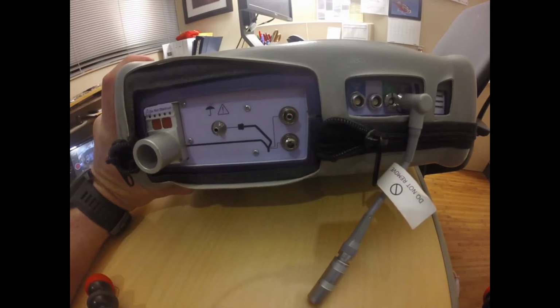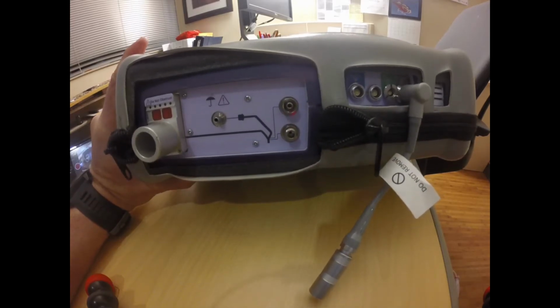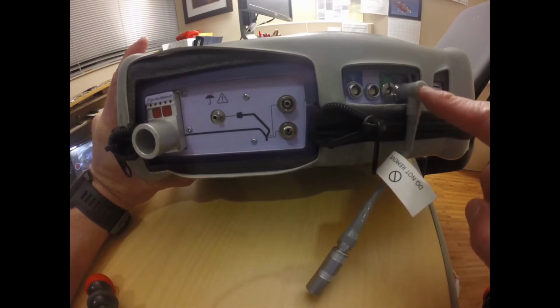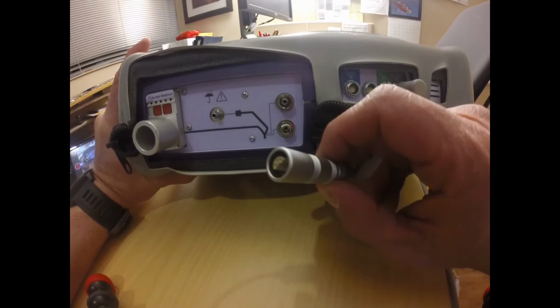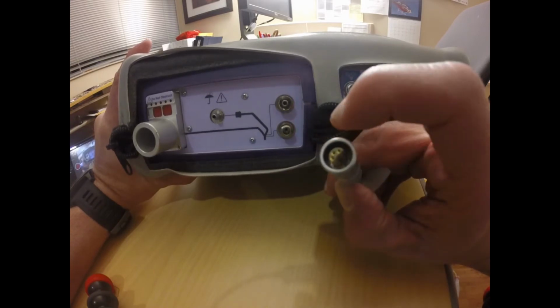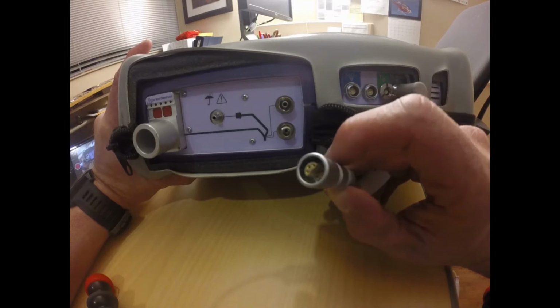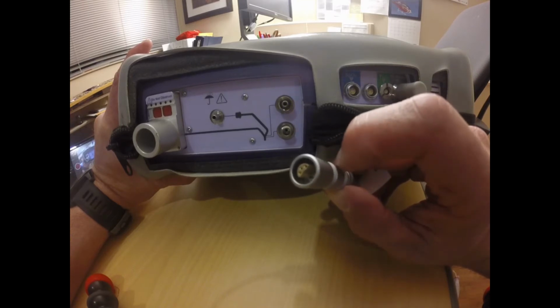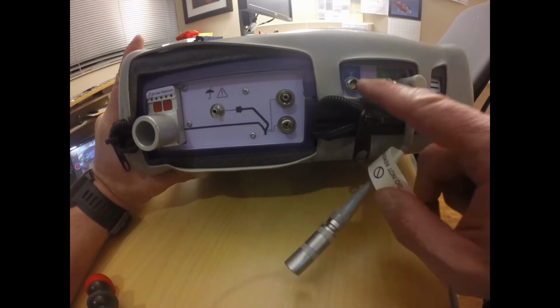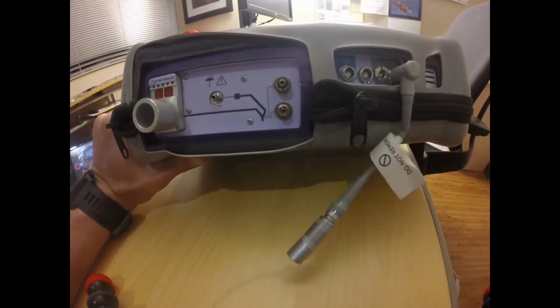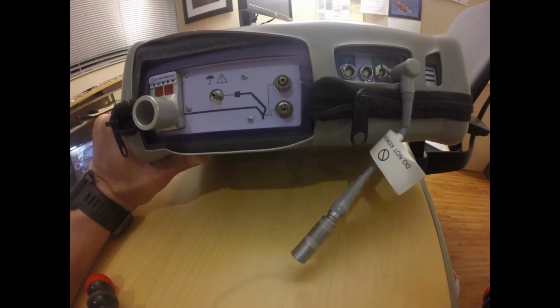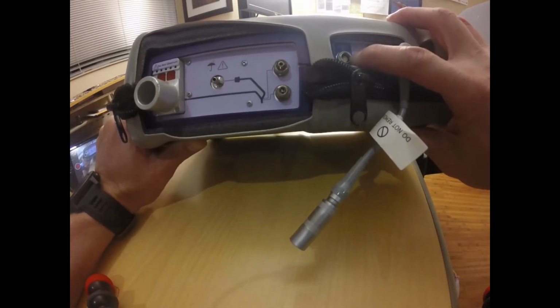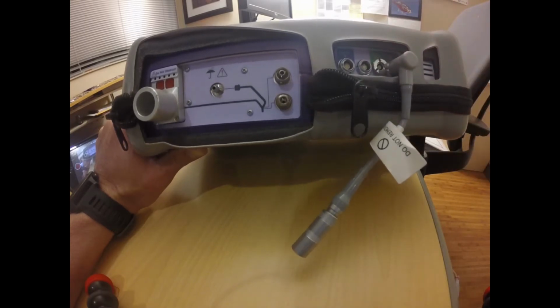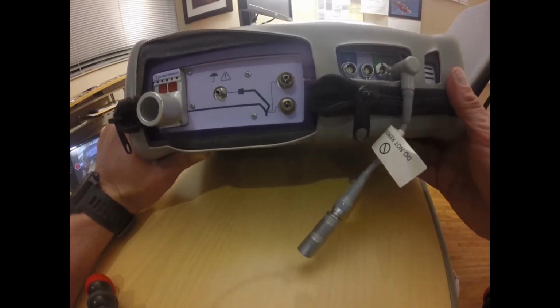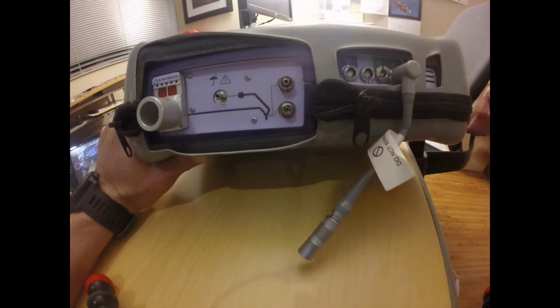The side of the ventilator has some very important pieces to it also. The first that I'll address is the charging port here. I will say that this tends to be a fairly sensitive piece right here, so please be careful when charging the ventilator or plugging it into external power. The other are inlets that we do not currently use. So one is the ability to monitor FiO2, another is pulse ox, and of course we didn't purchase those options with it. And then here is the portion where I'm going to hook my circuit up, which we'll go through.